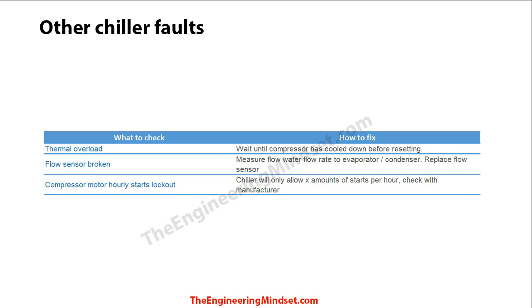One of the more common issues is a broken flow sensor, especially paddle-type sensors. Before a chiller starts, it checks for sufficient flow through the evaporator and condenser. If the paddle sensor loses communication or develops a fault and stops sending a signal to the control unit, the chiller will assume there is no flow and will disconnect itself, refusing to restart until sufficient flow is confirmed.